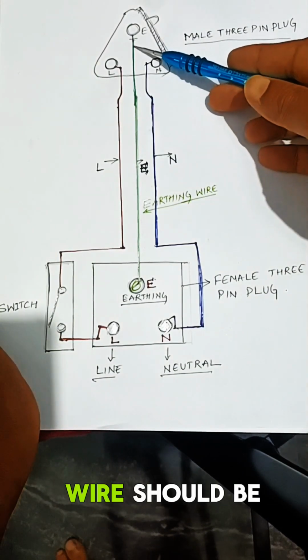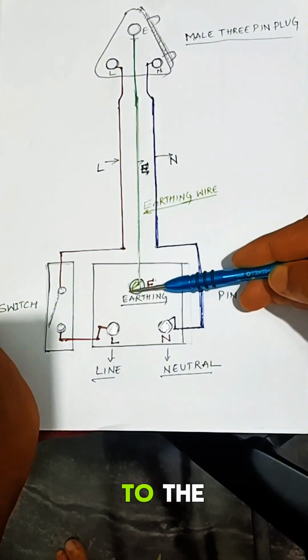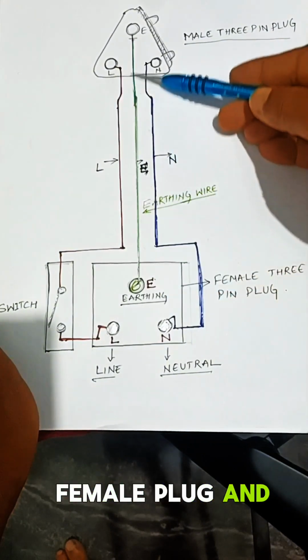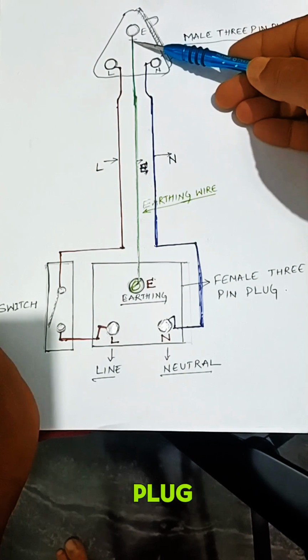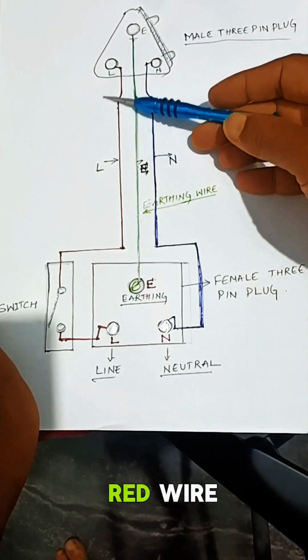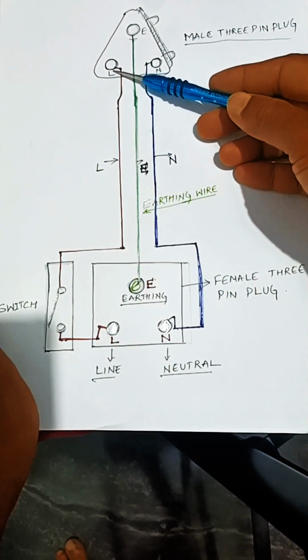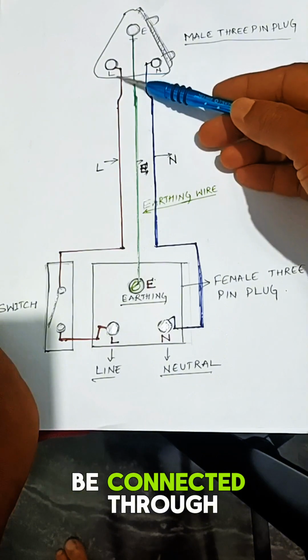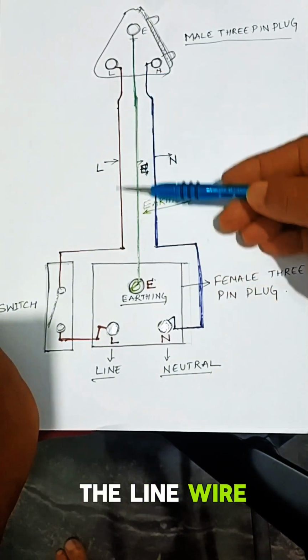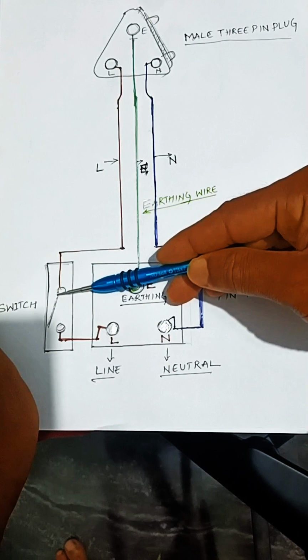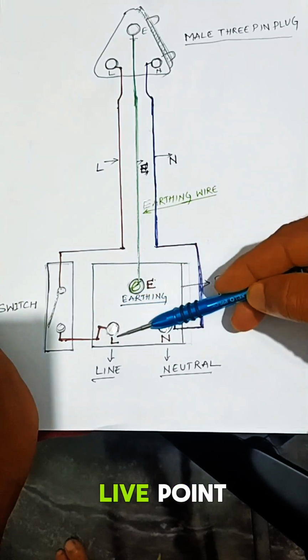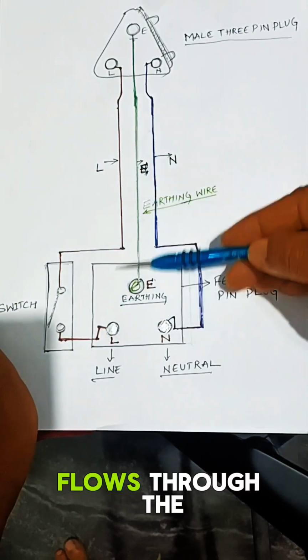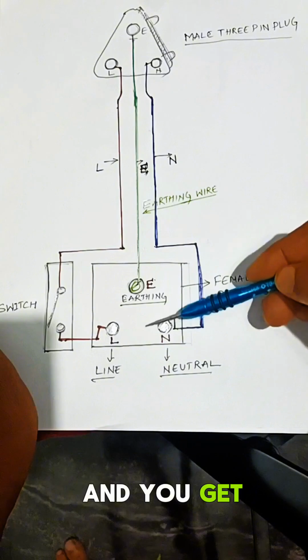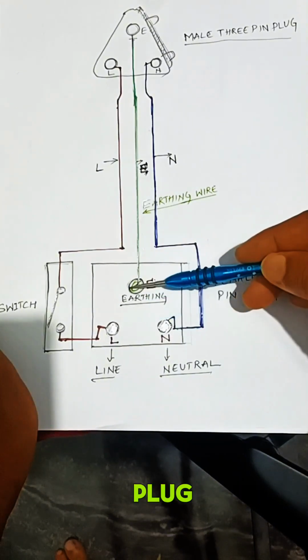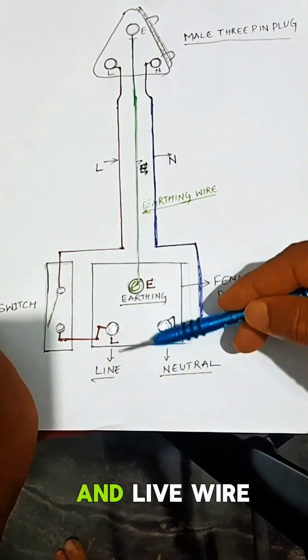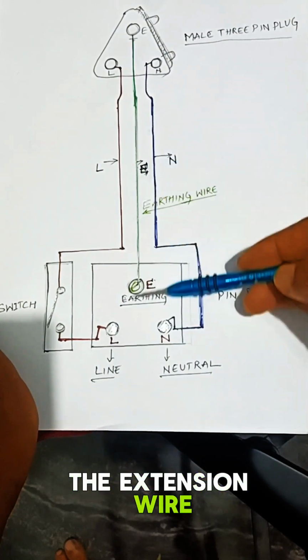And the earthing wire, the green color code, should be directly connected to the female plug and to the earthing point of the male plug. And the red wire, the line wire, should be connected through the switch. So this is the line wire, and through the switch we will connect it to the live point. When the switch is on, the current flows through the circuit and you get the voltage in this 3-pin plug. This is the earthing point, neutral, and live wire. This is how the extension wiring is done.